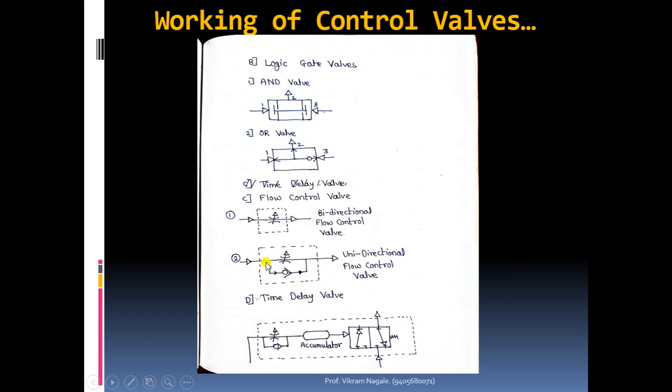Now what is this? You can see the direction of airflow is like this, left to right. It will come here, it will find some resistance over here. Resistance means what? Obstruction to the flow. Why? Because we are varying the cross section of that lining. Okay, so if the cross section is the same, obviously the flow rate will not change, means there won't be any resistance. But here if you are varying the cross section, means obviously there is a resistance, so air will try to move from this path, it will come in the parallel path.